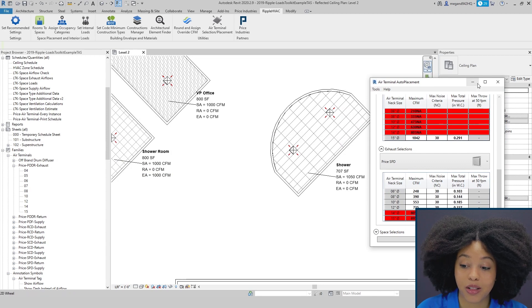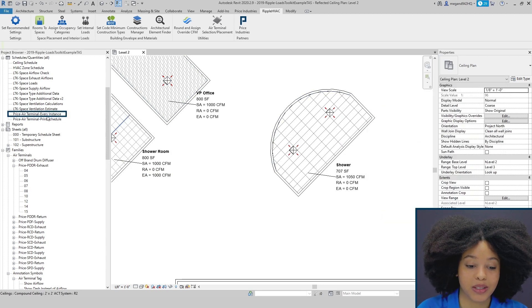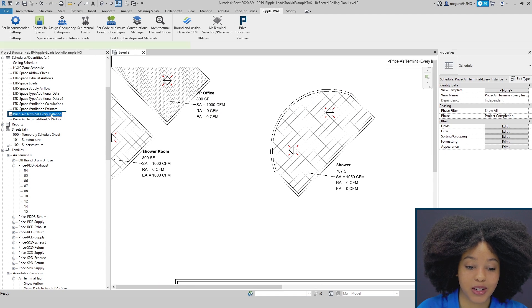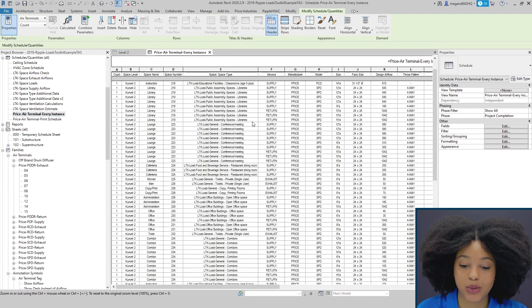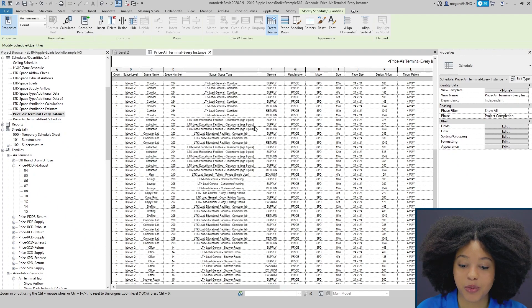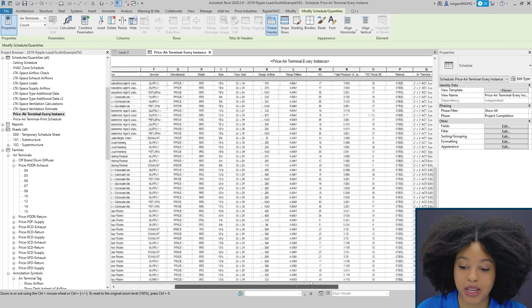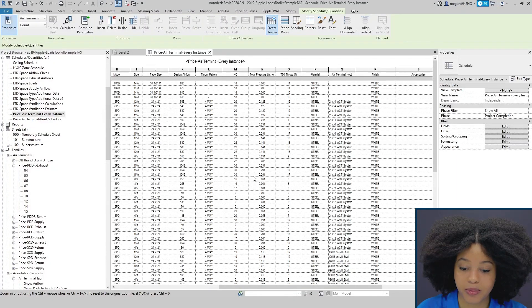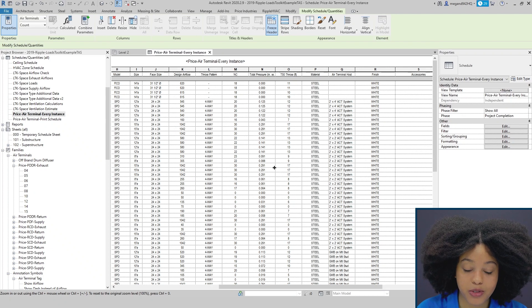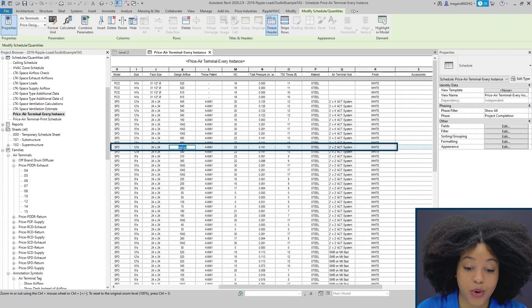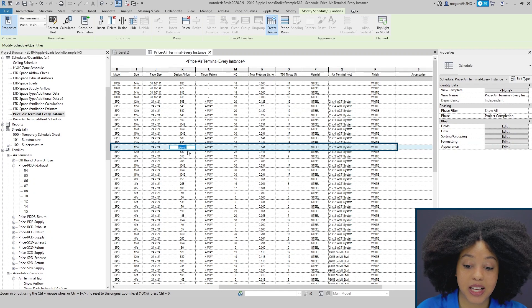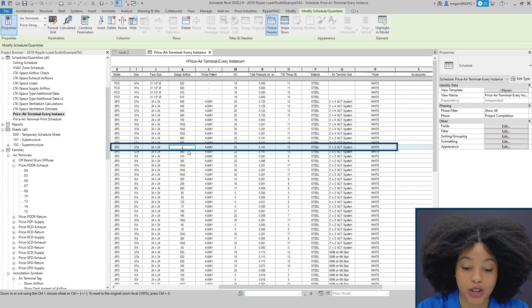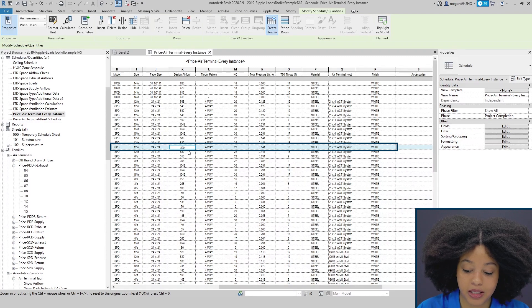Now that we have placed all our diffusers, we're going to take a look at the schedules. The very first one is the Every Instance Schedule. The Every Instance Schedule you can see here has information about every single diffuser that is currently placed in the project. Here you can see we also have performance for the different tools. The value here is if you are to change the CFM for a specific diffuser, you will also see that your performance auto-updates.